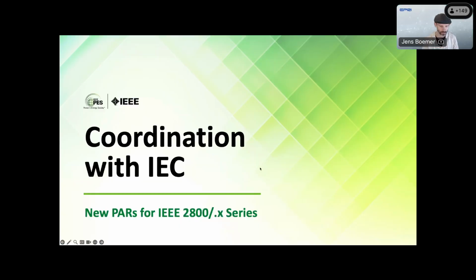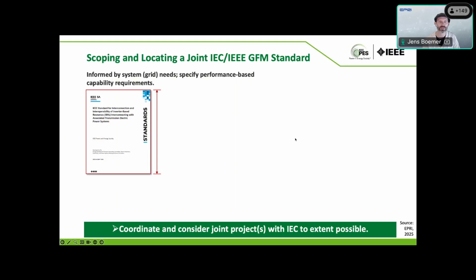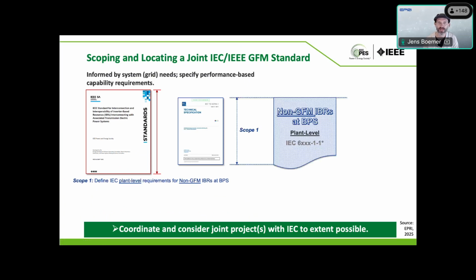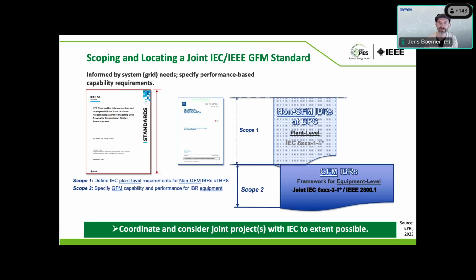Now, coming closer here to the end of my presentation, we're also trying to coordinate this grid forming recommended practice with the IEC. One of their challenges is that they currently do not have an interconnection standard like IEEE 2800 in their system. So they may be starting out with a technical specification that is currently focused on distributed energy resources. That would be the first scope for them to translate some of the 2800 into that context.